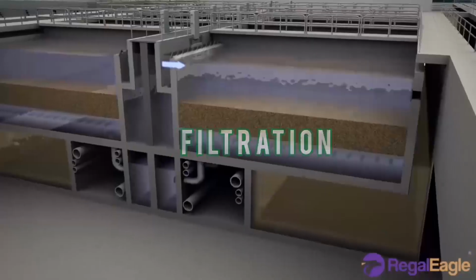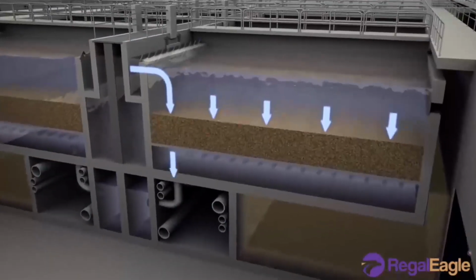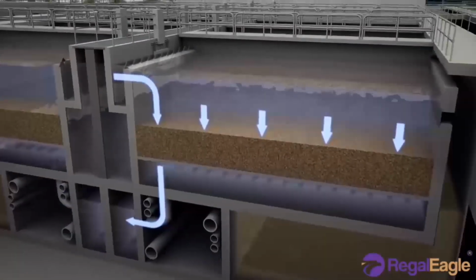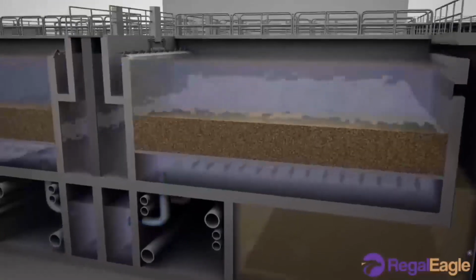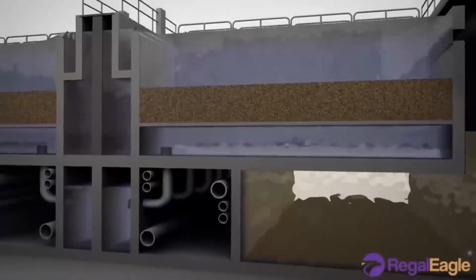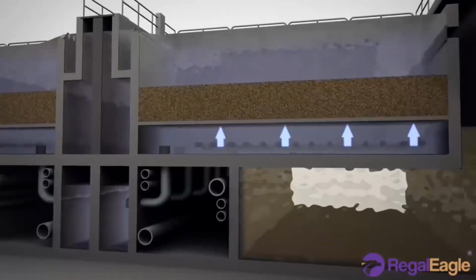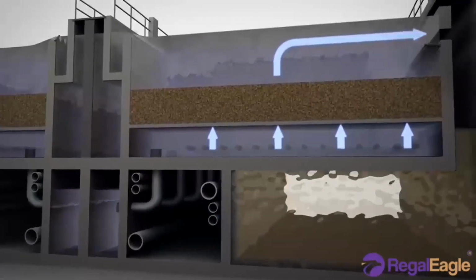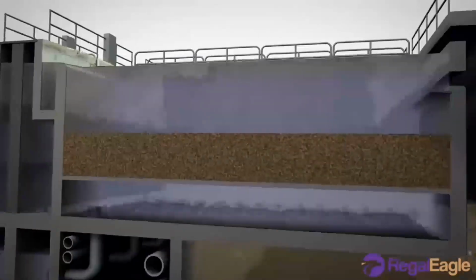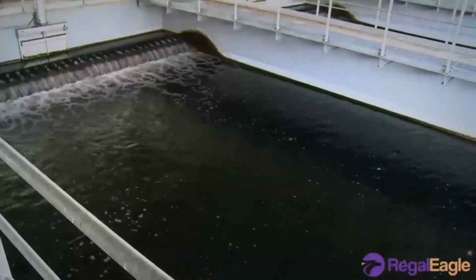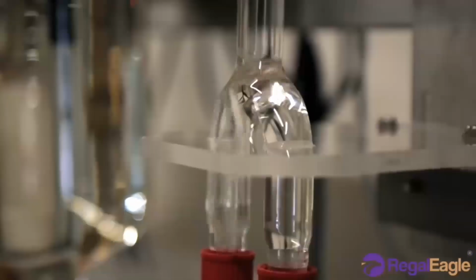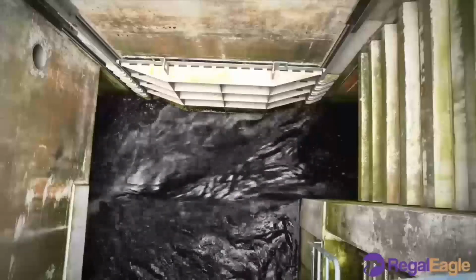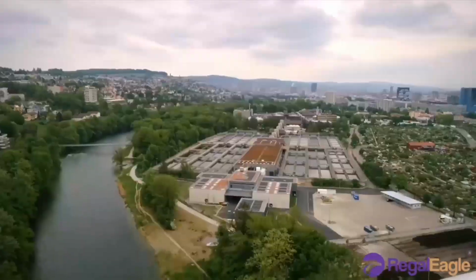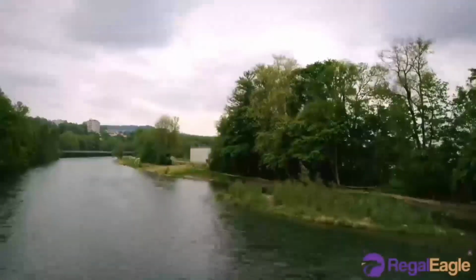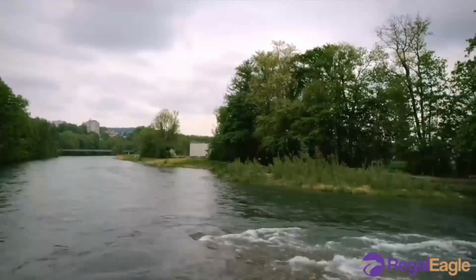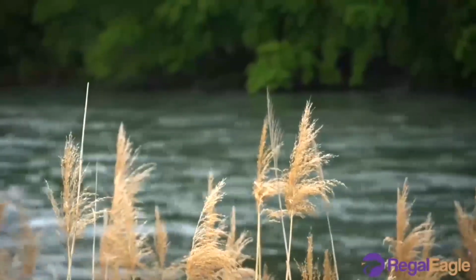Filtration. Filtration is the process where solids are separated from a liquid in water treatment. The solids that are not separated in the sedimentation tanks are removed by passing the water through sand and gravel beds. Rapid gravity filters are often used. When the filters are full of trapped solids, they are backwashed. In this process, clean water and air are pumped back up the filter to dislodge the trapped impurities, and the water carrying the debris is pumped into the source river after a settlement stage.